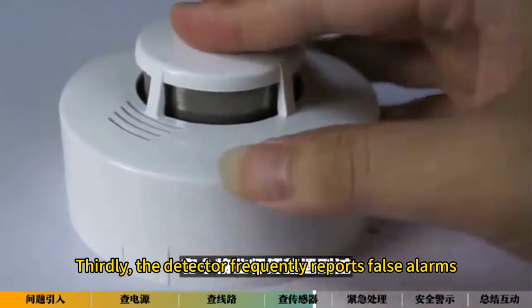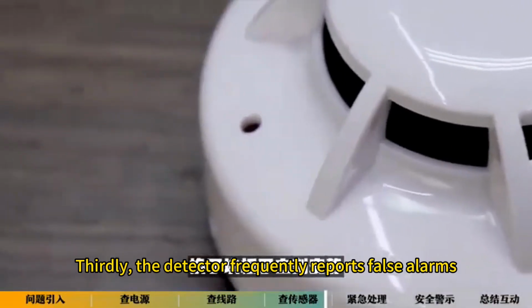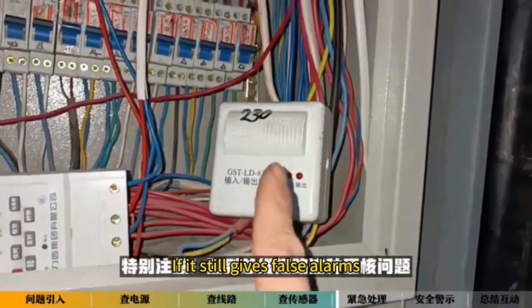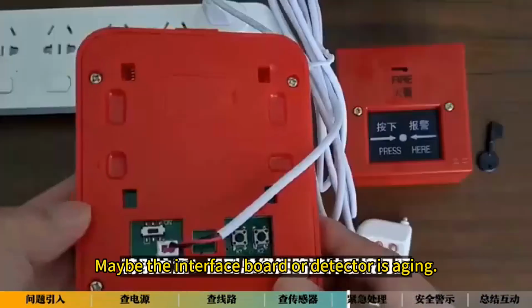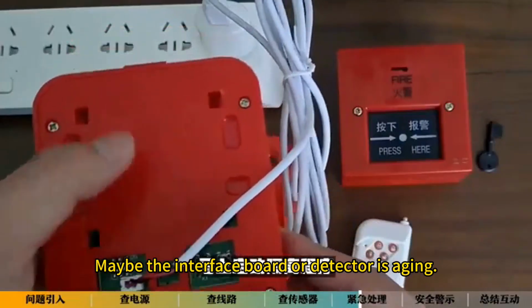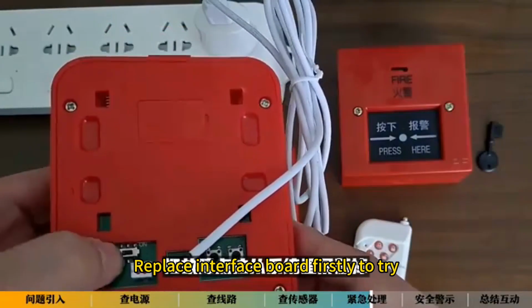Thirdly, the detector frequently reports false alarms. Remove it and reinstall it. If it still gives false alarms, maybe the interface board or detector is aging. Replace the interface board first to try.